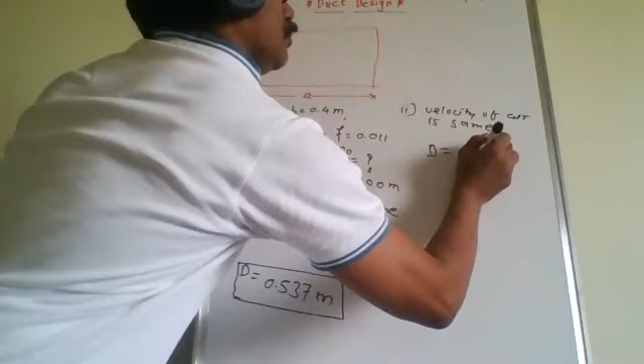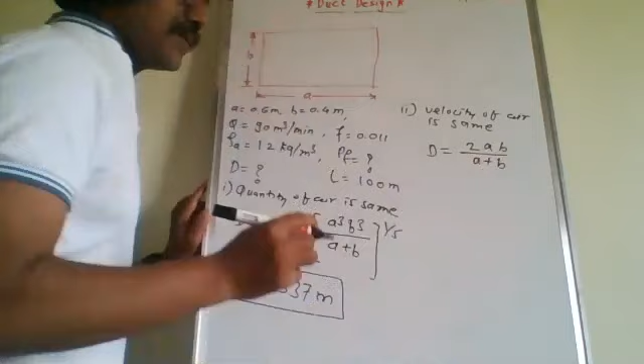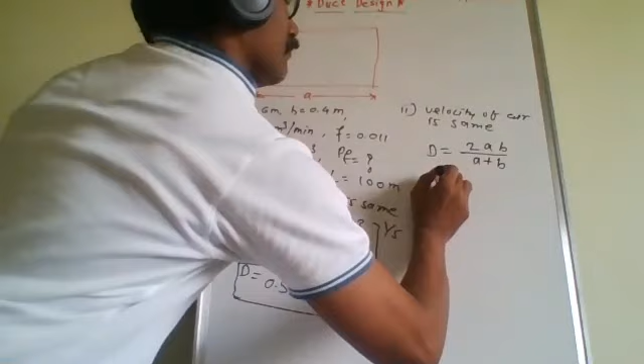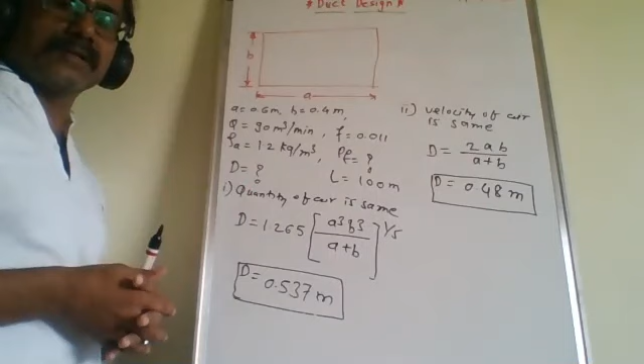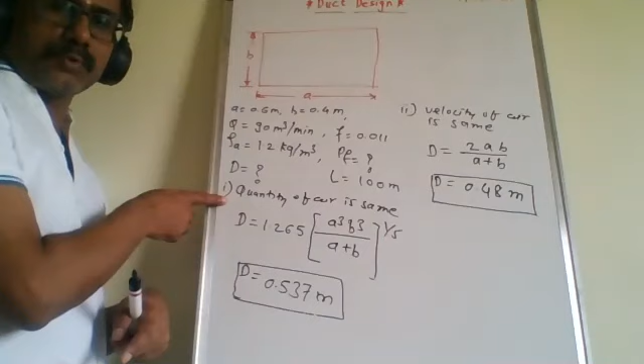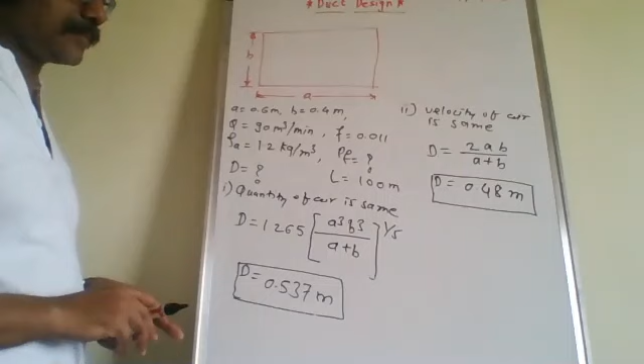So for this, the equation for the equivalent diameter D is very simple: 2AB divided by A plus B. Very simple equation to remember. So just put the numbers for A and B, 0.6, 0.4, and get the diameter D. That is 0.48 meter. So the first part of the problem is to calculate the equivalent diameter when flow rate, quantity in both the ducts, is same, and when velocity in both the ducts is same.